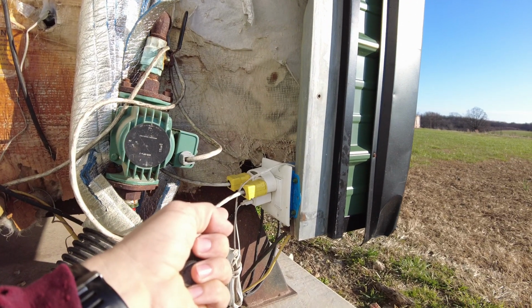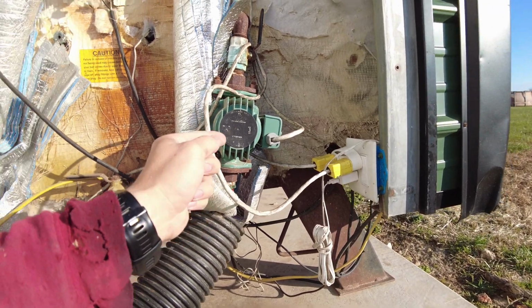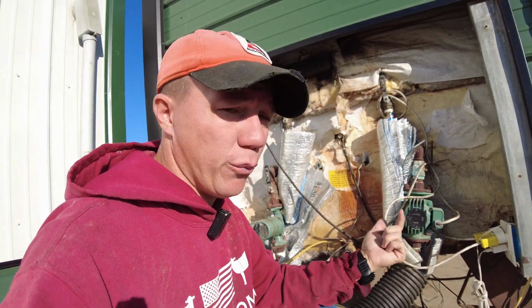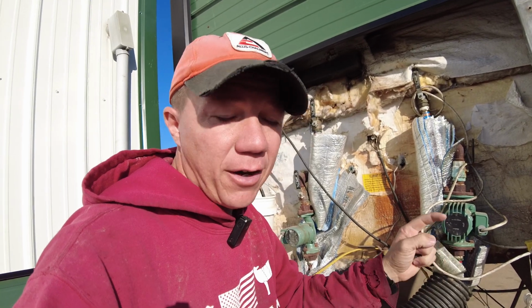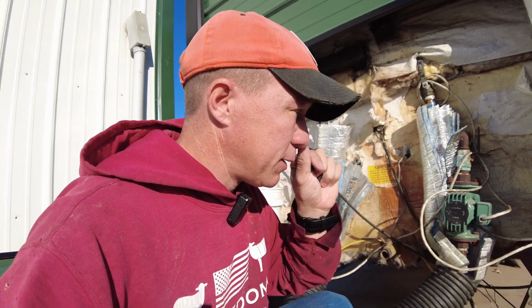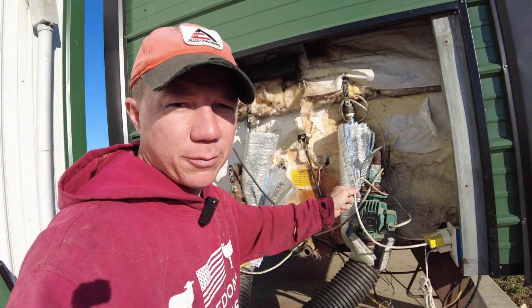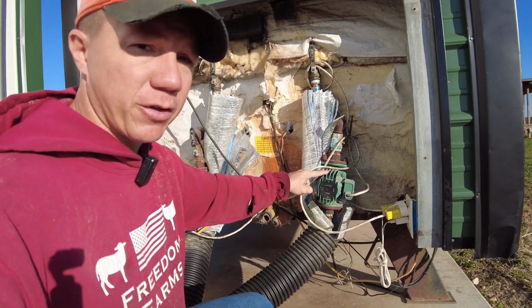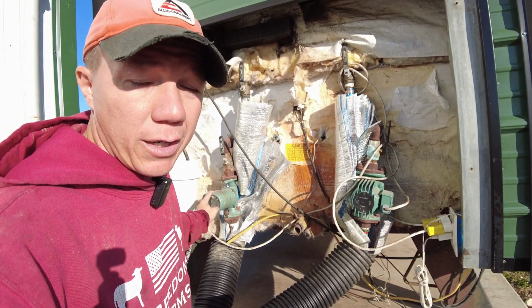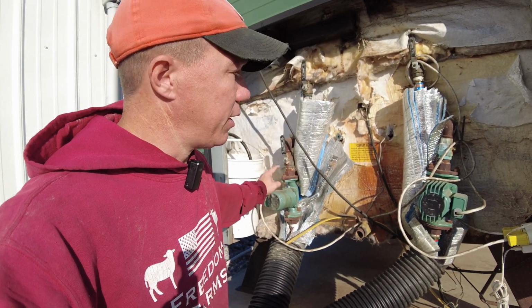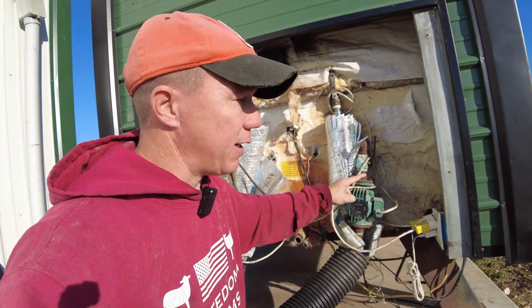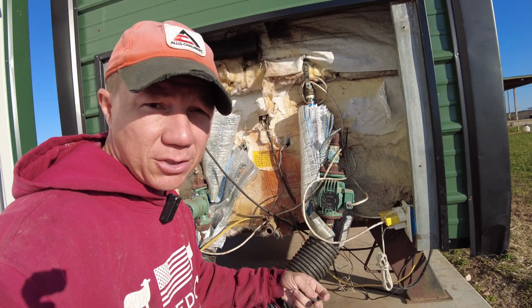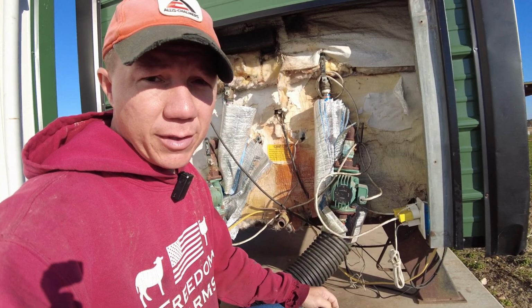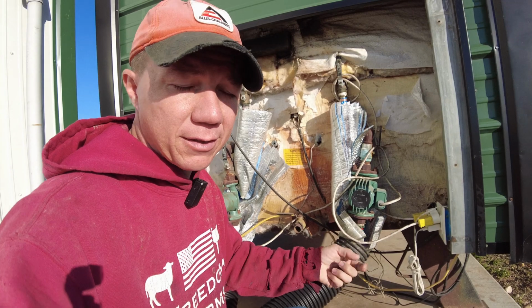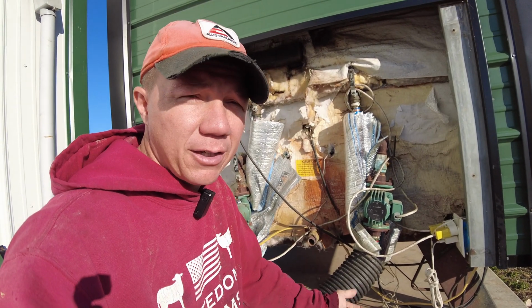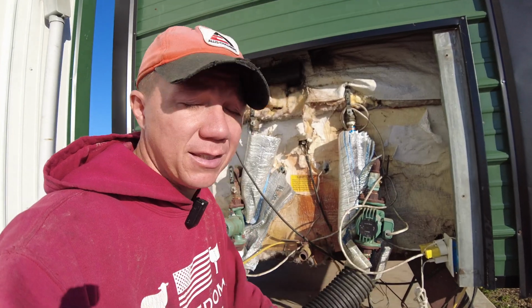We have them wired to where they plug in. So I do it like this for two reasons. One, if I don't want to run one pump, it's easy just to unplug it. The other reason is because if a pump fails, the lengths of these plugins are the same on both of them. Let's say that the pump for the house fails, I can pull the one off the shop, where I don't need heat, I just like to have heat, and put it back on the house until I can get a new pump. Now I do keep another pump on hand just because of that potential, but it's not a bad thing to have a backup because I don't want to use the electric heat if I don't have to. But at the end of the day, if I had to use the electric heat for 2 or 3 days to get a pump, it's not the end of the world either.